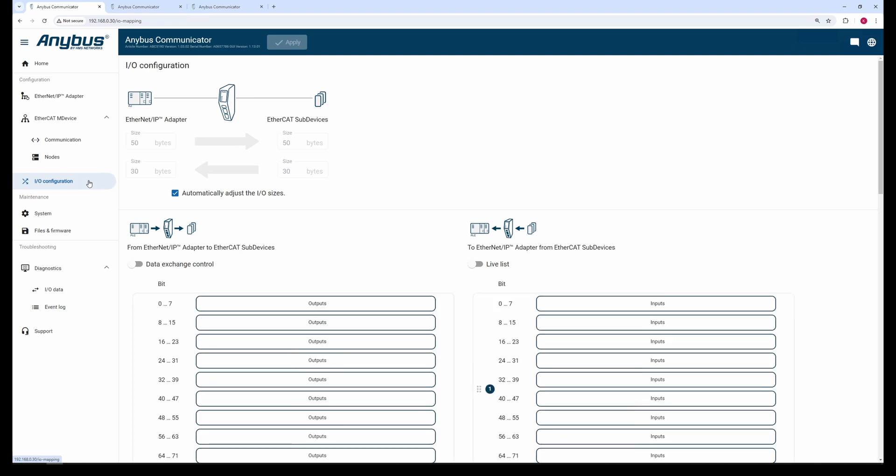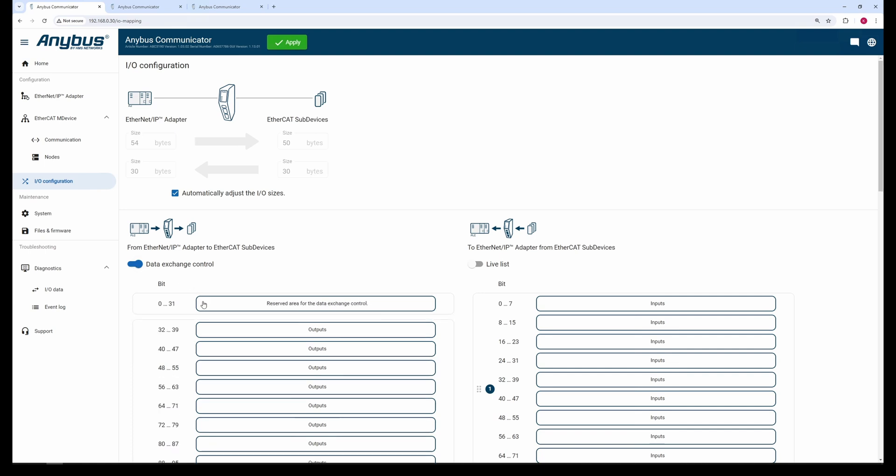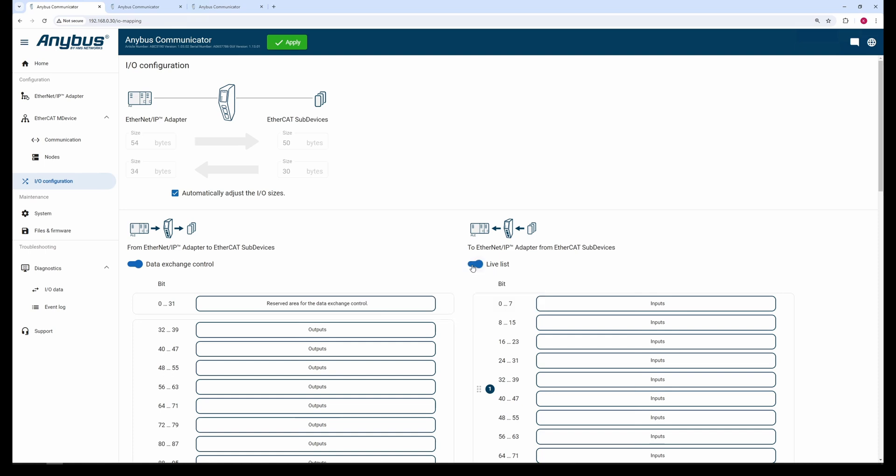Head back to the I/O configuration tab. Let's enable the Data Exchange control. This allows you to control when the main device shall exchange data with the sub-devices. While here, let's also enable the Live List, that allows the other network to see which nodes are active and exchanging data. You may control up to 32 sub-devices and see the status of the same.